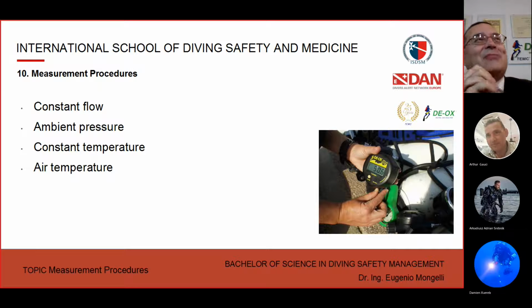So I was telling you the funny story that happened to me last September. We attended the ADEX show in Singapore. We provided some gas analyzers, NITROX, helium and oxygen analyzers, to some diving centers of the area. So they came back to us and said, hey, we are calibrating the analyzers at 20.3% of oxygen, and then the reading is not good. I said, sorry, why are you sure that you have 20.3%? Do you have a sample gas? No, we just use ambient air, and ambient air at 90% humidity, at 35, 36 Celsius temperature. So we have around 20.3% of oxygen.